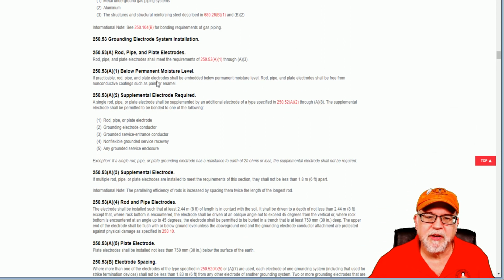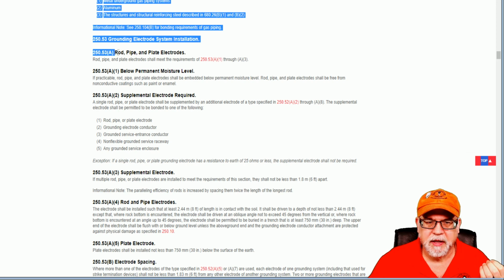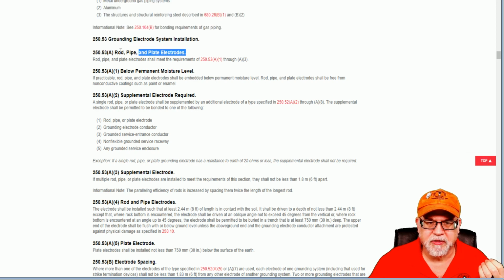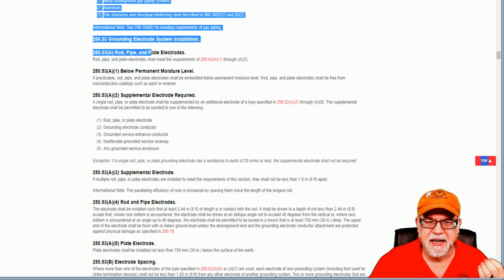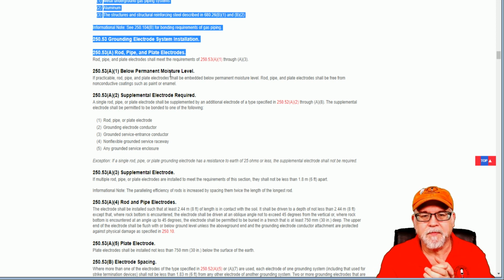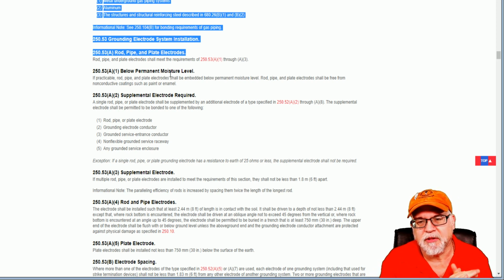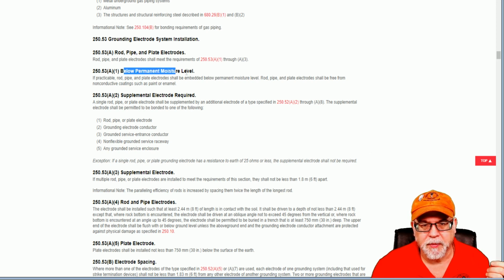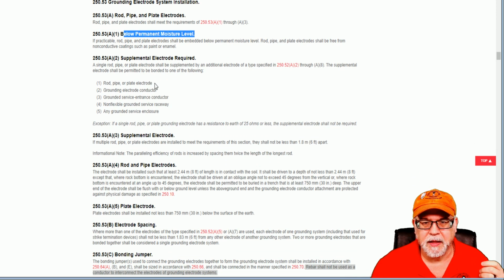Now, when we're talking about what we just said a minute ago, we want to talk about this, and that is 250.53(A) when it deals with rod, pipe, and plate electrodes. So very specific right here, and I don't know why I'm having highlighting issues, but there we go. It says rod, pipe, and plates shall meet the requirements of 250.53(A)(1) through (A)(3). All right, so again, be installed below the permanent moisture level. I don't think I see people doing that all the time, but there you go.